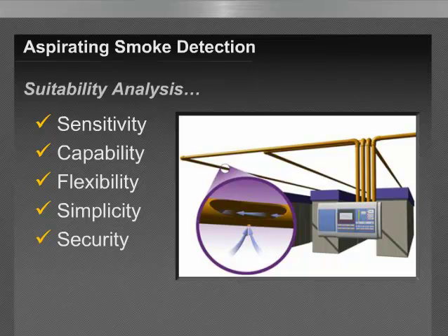And when we talk about flexibility, we talk about having multiple alarm thresholds to stage responses, flexible sampling configurations, or the ability to place the sampling in environmental conditions, such as high temperature environments, that will otherwise impede the performance of traditional measures. Simplicity: it's low maintenance, with ease of maintenance, and the accessibility is greatly improved compared to traditional measures, as we'll show in some following slides. And as well, the security, and that is accessibility without disruption of operations. To get to the detector to test, inspect, and maintain it becomes a lot more manageable in respect of its application.